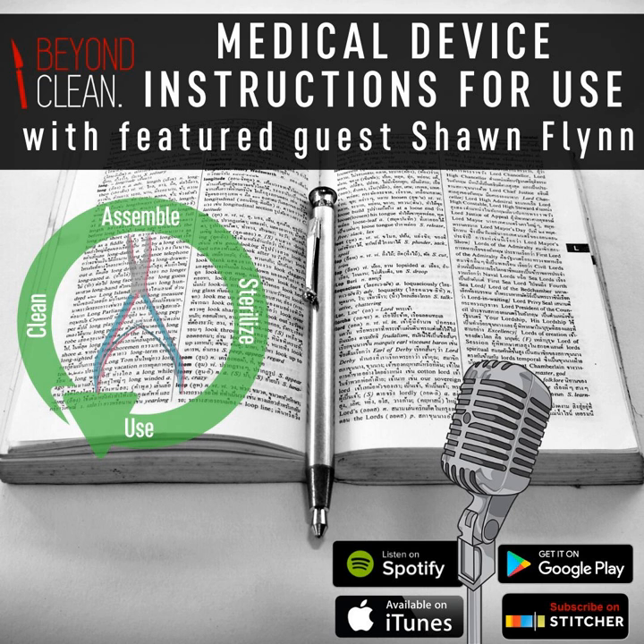So knowing the predicates, and having the expertise with the FDA reviewer and consultant we were using, we compiled our 510(k) at the same time we were building our quality system. That helped tremendously as well, because within the 510(k) clearance application you actually have to have a risk hazard analysis, which illustrates the risk the device poses to the patient and or the user. That tied in well with our quality system at the time.